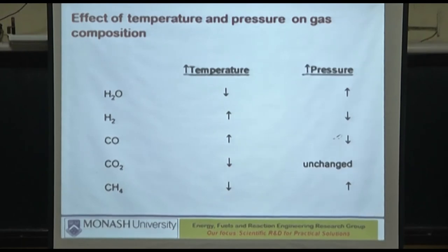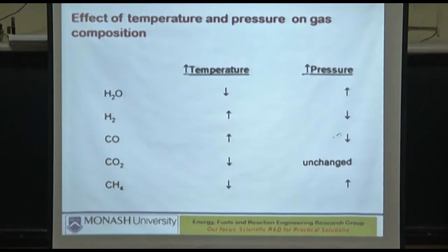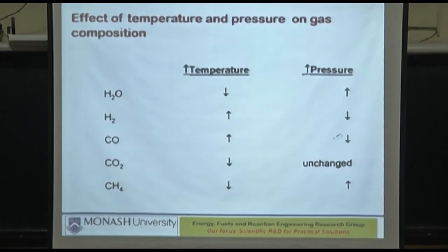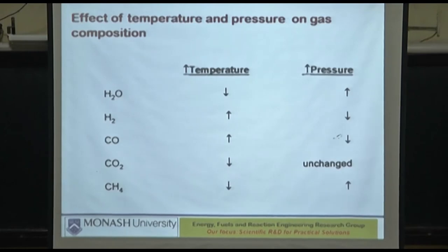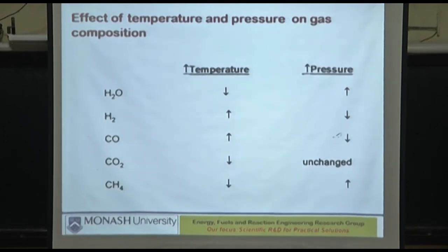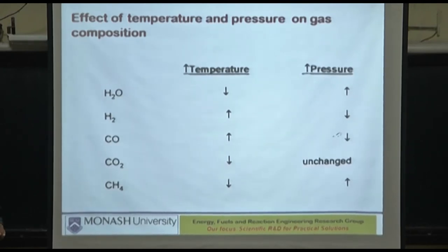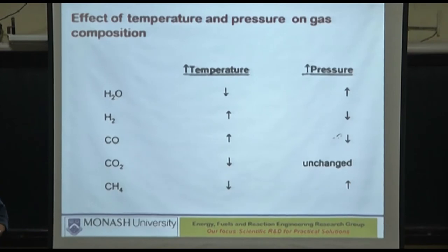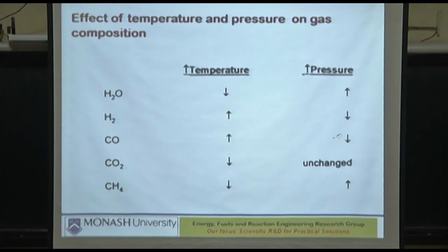so that you still get a good amount of combustible constituents, carbon monoxide and hydrogen, and that will give you a certain calorific value in megajoules per kilogram that is combustible in the gas turbine. So for example, the gas turbine manufacturers will tell you that as a rule of thumb, they require about 3.7 megajoules per kilogram. However you have it, with whatever combination of hydrogen, CO and methane you have, it doesn't matter to them all that much.